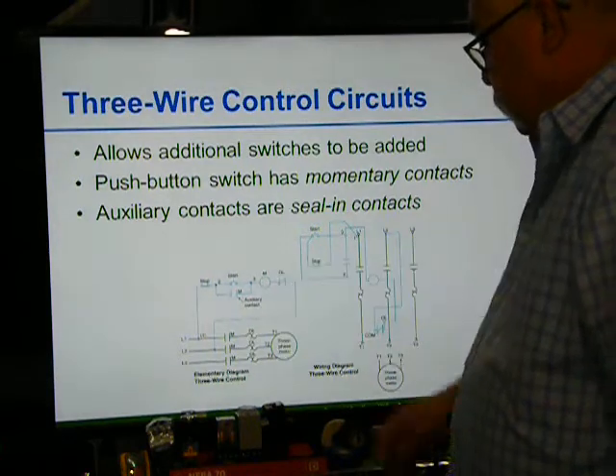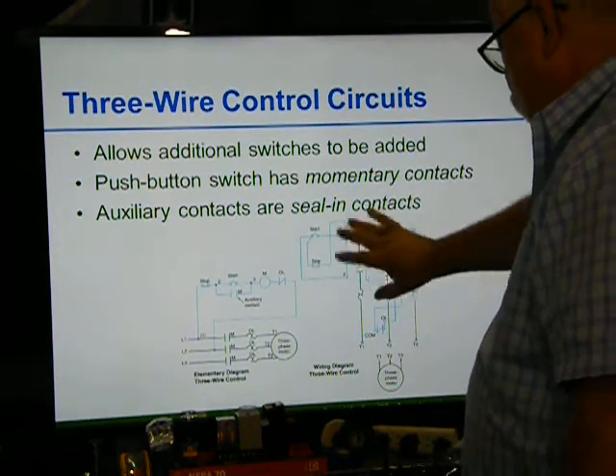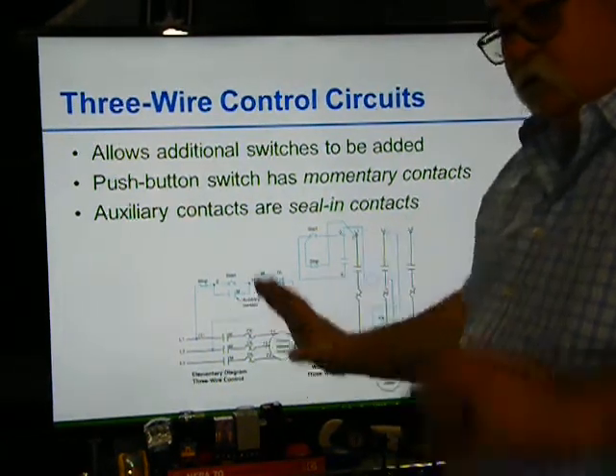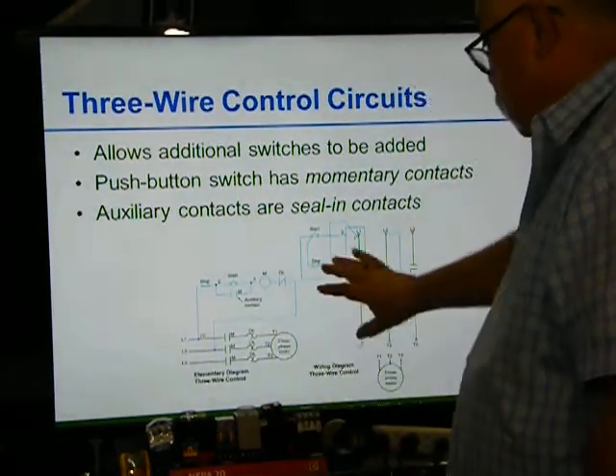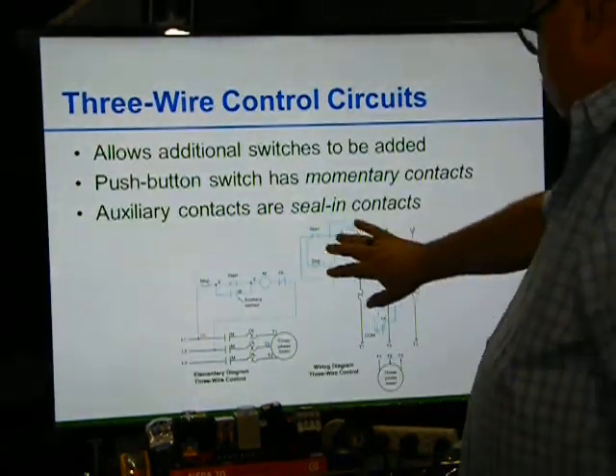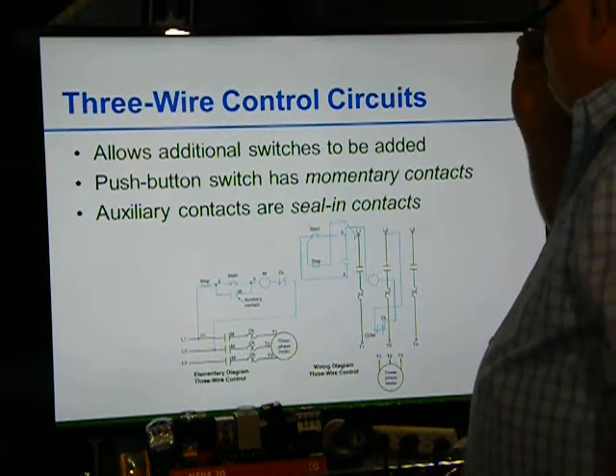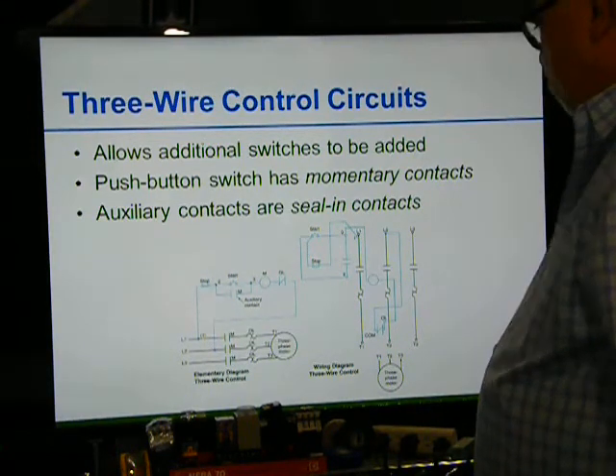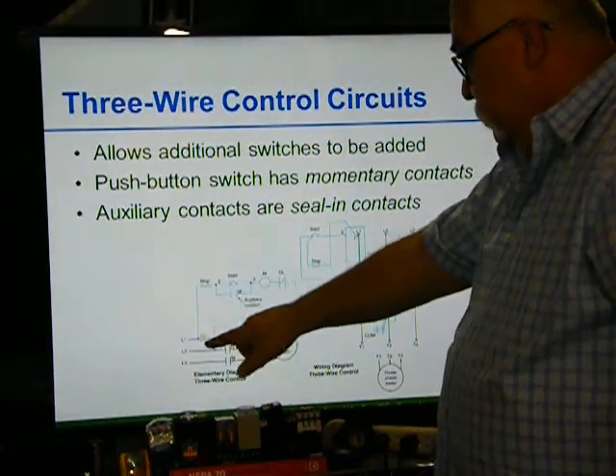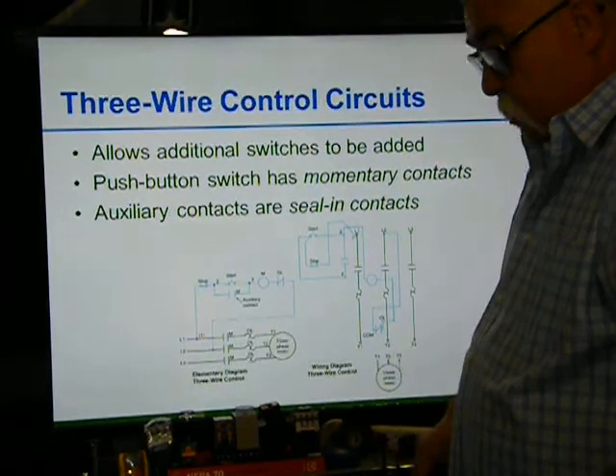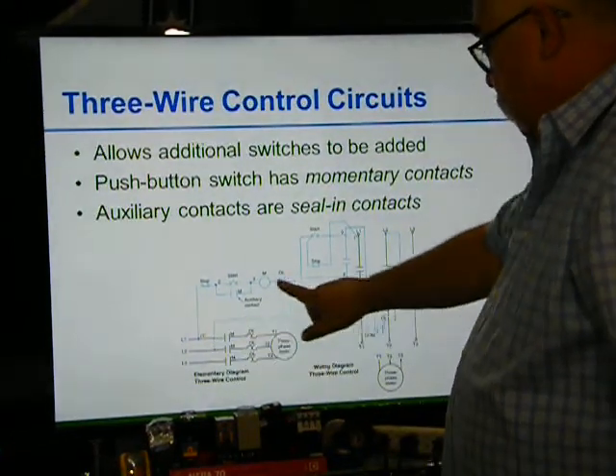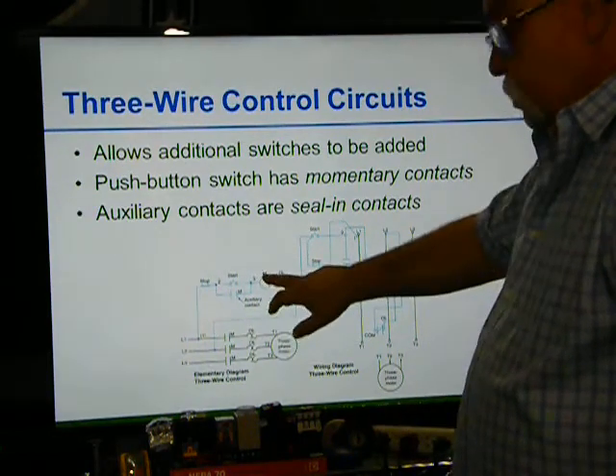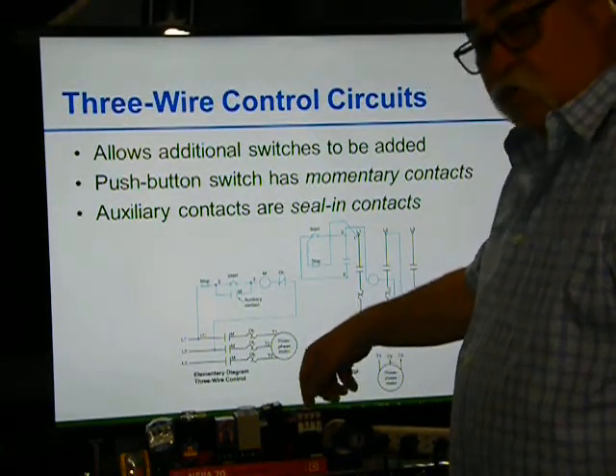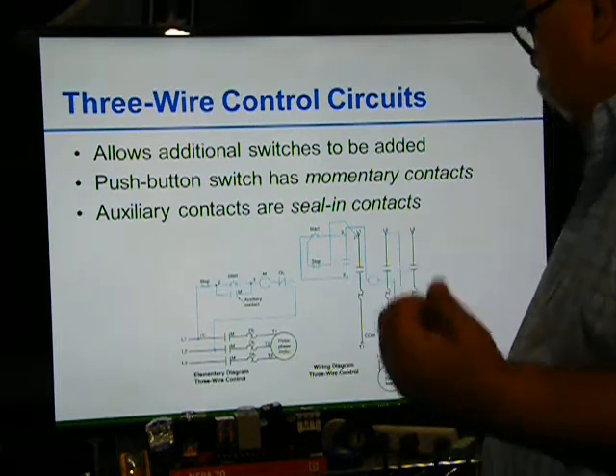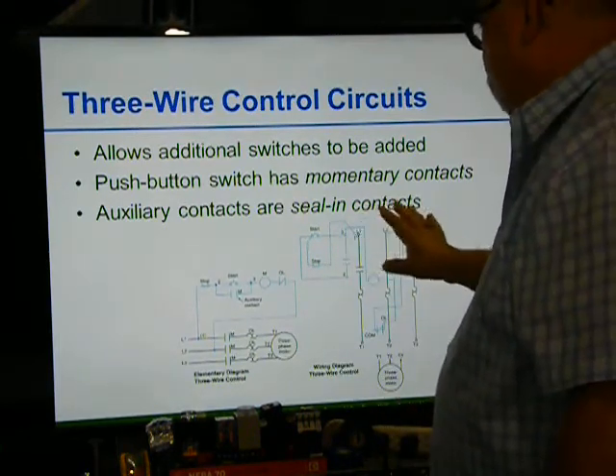This is a wiring diagram, and this is an elementary diagram. They're both the same thing. This is showing within the component. The difference between the two is this is somewhere else, and this is within the unit itself. So there's no difference, just a wiring diagram. This is the one that I always put up on the board. Got my hot coming here because this one is 208 or 230 volts. Comes across and feeds this side. Even though it says M here, it's not the motor, it's the coil. But once this coil closes, guess what? The motor comes on. So that's why they use M. Some of them use a C, some use an M. So auxiliary contacts are sealed in.